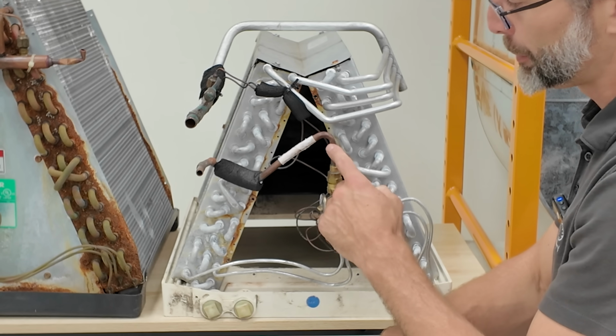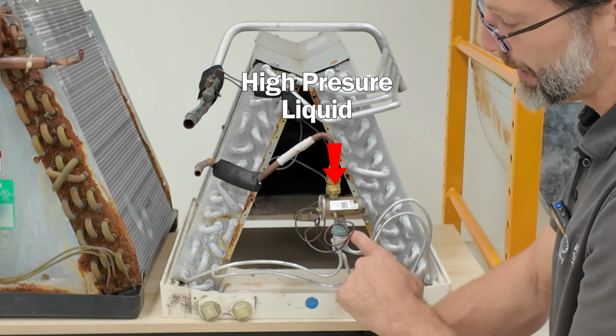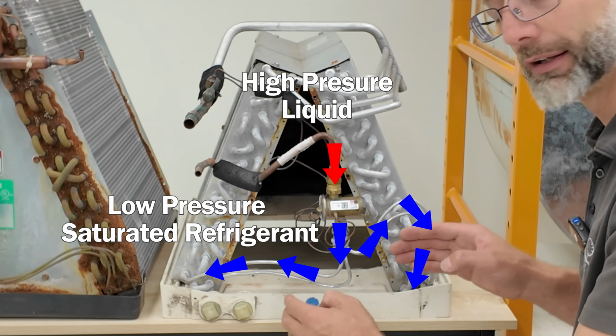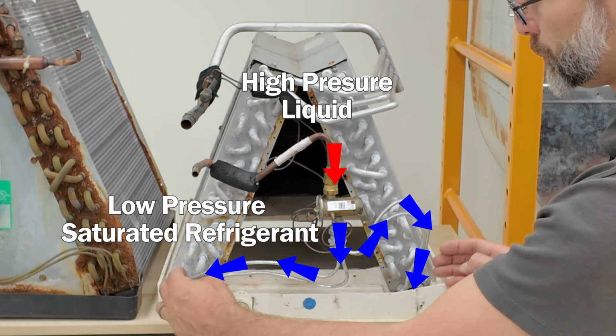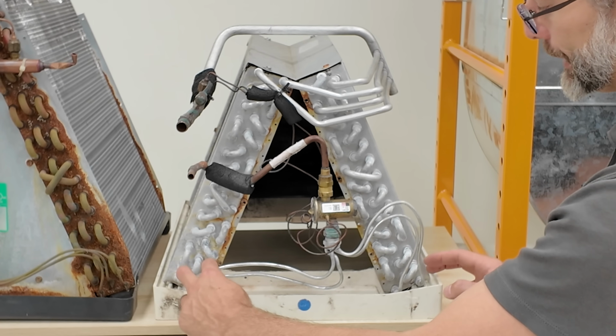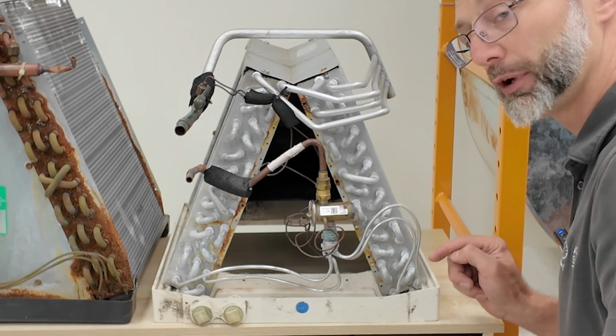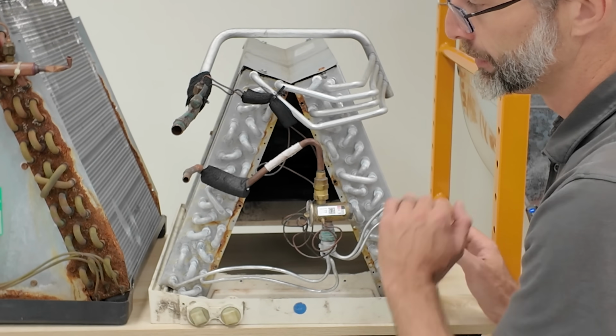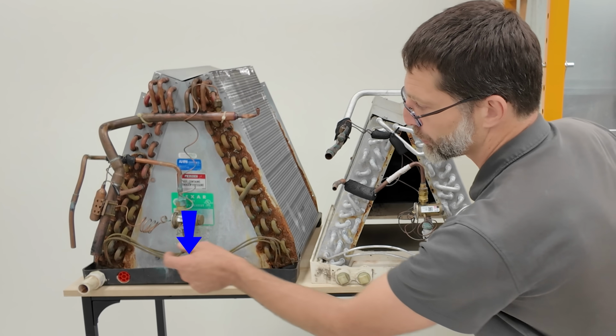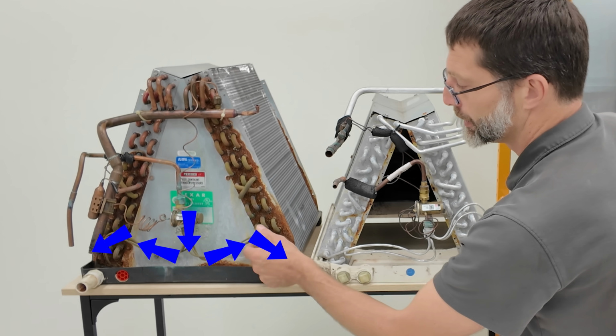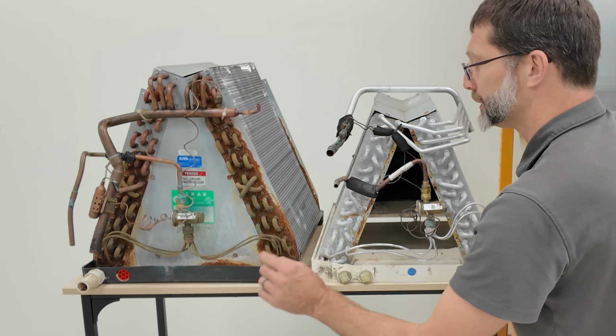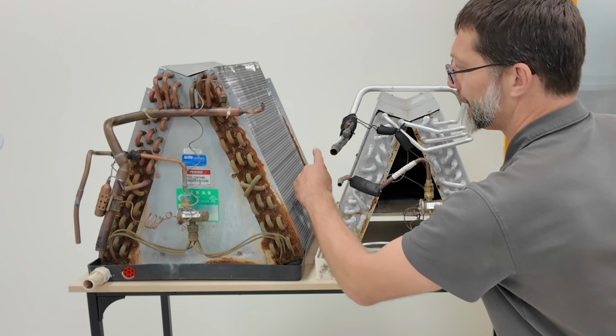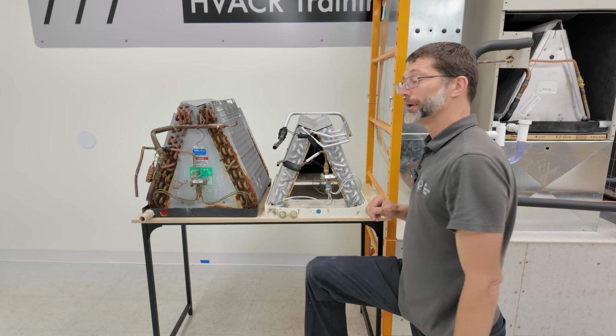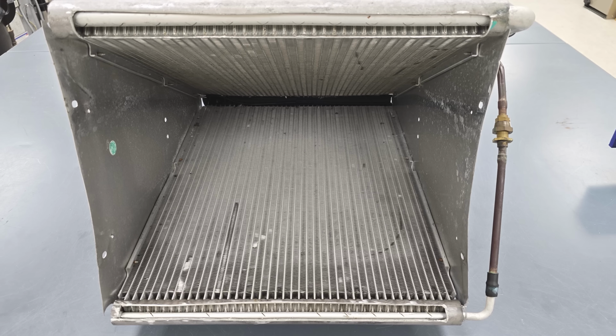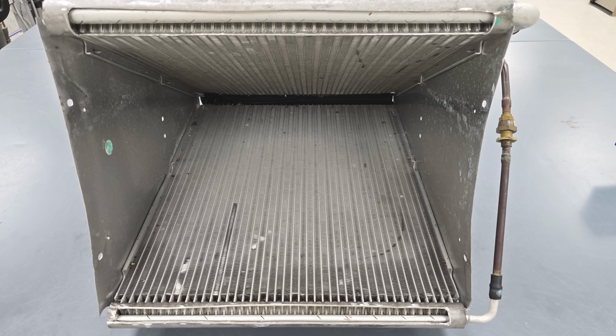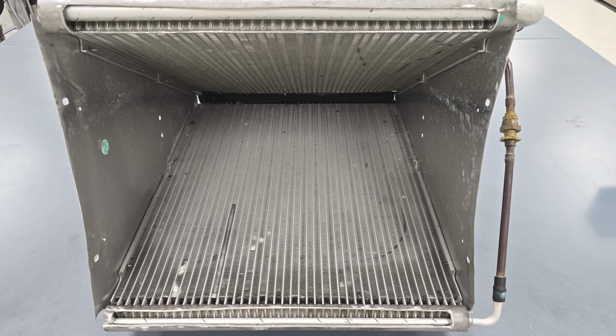You have your high pressure liquid entering, and then you have low pressure saturated refrigerant exiting. It's going to exit through these distributor tubes over to the coil, and then there are going to be 4 tubes that the refrigerant is going to be traveling through the coil. On this one, there are 6 tubes right here, so 3 here and 3 here. So it's going to be traveling through 6 tubes, 3 on each side, whereas with the microchannel coil, there were 1,025 pathways for the refrigerant to be traveling through those little microchannels.